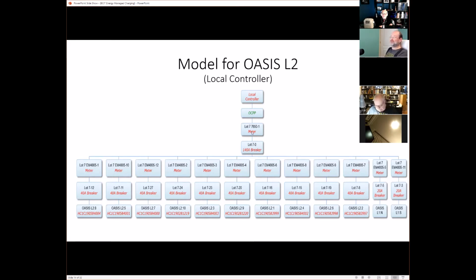Above that, we have another meter, which is measuring the consumption of the entire panel, and it also doubles as a way to do protection on the upstream transformer. Transformers use the kVA measurement, and that's what they're rated in. So we can put a limit at this meter point. Say the upstream transformer is a 75 kVA. We would want to put a limit in kVA somewhat less than 75 kVA, and we will protect that. We will prevent more power than 75 kVA from being used by the EV chargers.